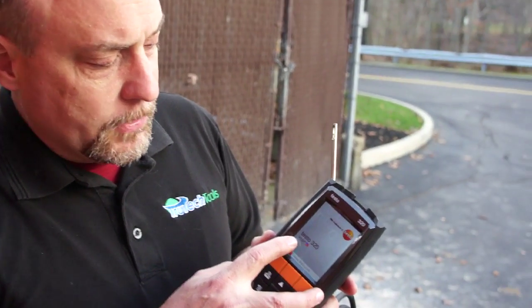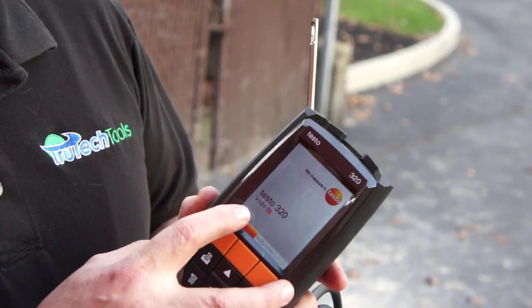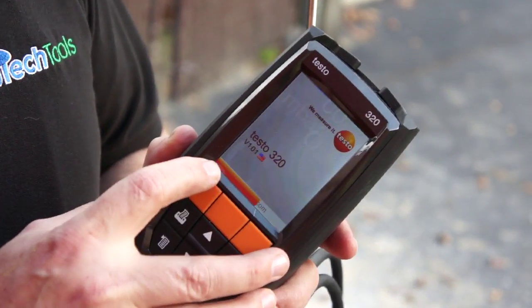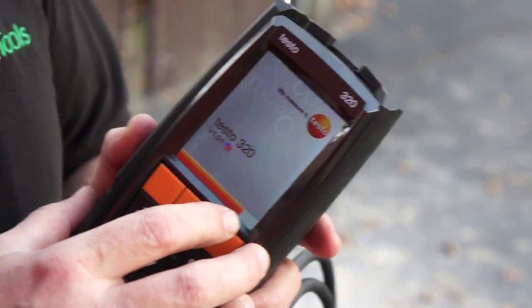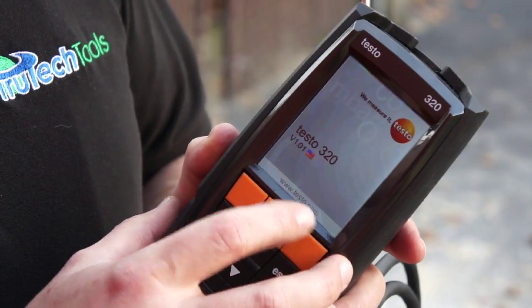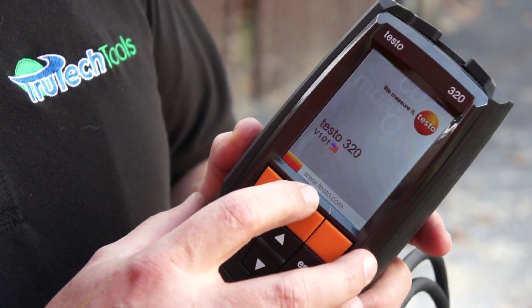Alright, an important thing to remember with any combustion analyzer is that it needs to be zeroed in fresh air. So we stepped outside for a minute just to let the instrument go through its initial calibration. I'm going to go ahead and turn the instrument on, pressing the power key. When the instrument powers up, you're going to see, first of all, Testo 320. You're going to see the firmware version, which is 1.01, and you're going to see it start going through its warm-up on the bottom of the display. It's going to go through this a couple of times. We'll see this go through.